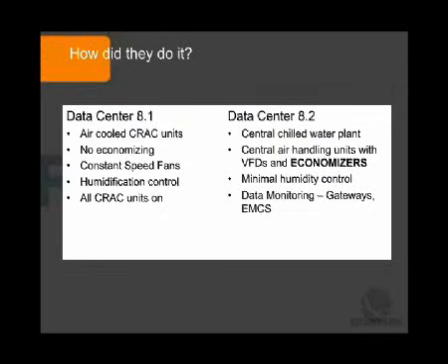Now, in this case, if you compare, let's say, these two, which have such a huge difference in the HVAC energy, the bad one uses standard air-cooled CRACs, no economizers, constant speed fans, and keeps everything on all the time, including a lot of humidification. The efficient one saves over half the HVAC energy with a central chilled water plant, airside economizers, variable frequency drives on the central AHUs, not much humidity control, and they monitor their data and respond accordingly. It's not that hard.